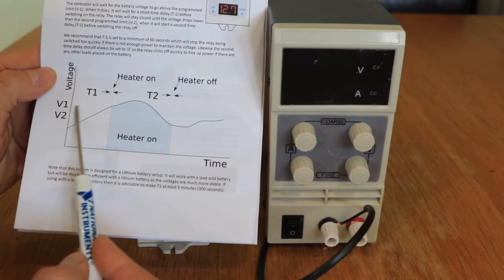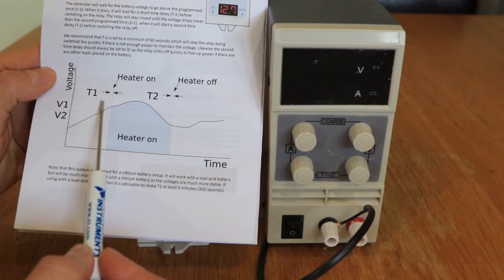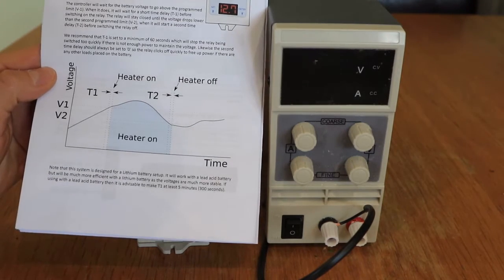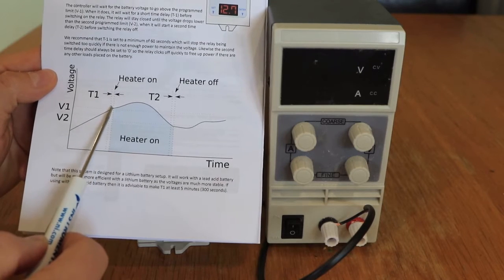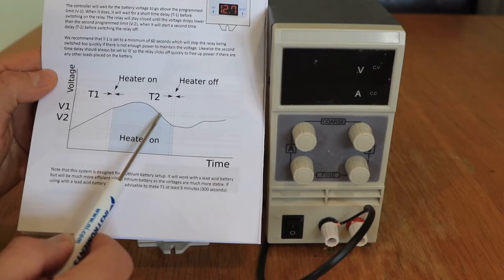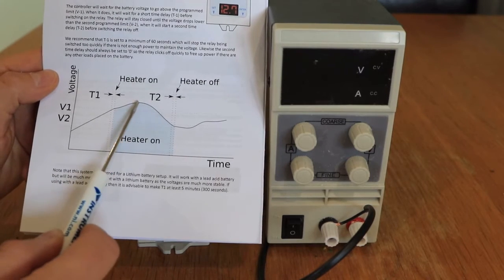We've programmed V1, which is a turn on voltage. This then triggers a time delay, so the controller is going to count down a time between the voltage level being reached and the relay actually turning on. It then turns the relay on, which turns the heater on. This is the point where the heater is heating and we've got lots of energy coming in, for example from the sun.